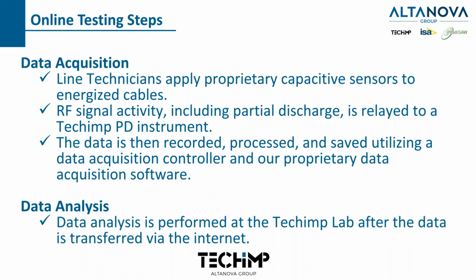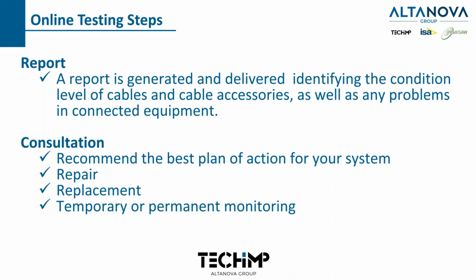So the steps are basically this. Our technicians go in and apply a proprietary capacitive sensor just below the termination, around the shielded part of the cable. I'm going to show you some pictures in a minute. Then we pick up any RF signal activity, and it's relayed to our data acquisition unit. We download it to our laptop and send it to our lab, where the analysis is done. Then a report is issued and we send the report to you. Usually we'll then have a consultation to recommend either repair or replacement. Repair would be for equipment such as transformers and switchgear, and replacement would be for terminations or cable, because you can't really repair a cable once it has a high level of partial discharge.